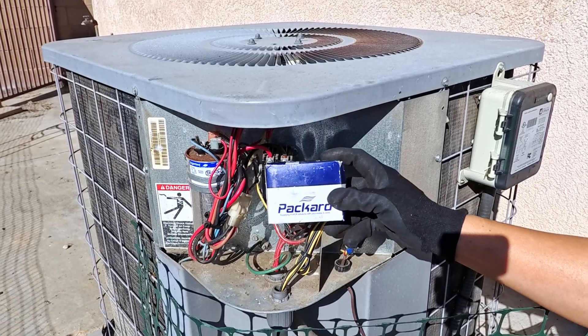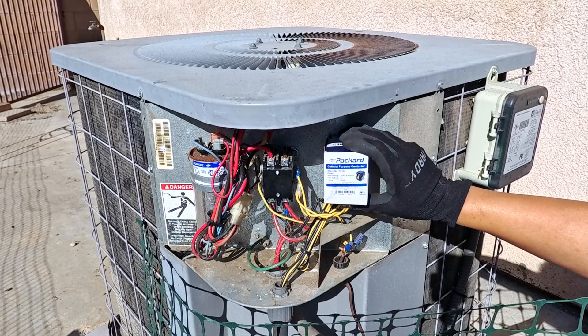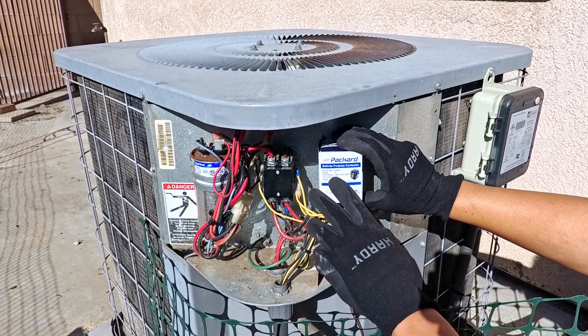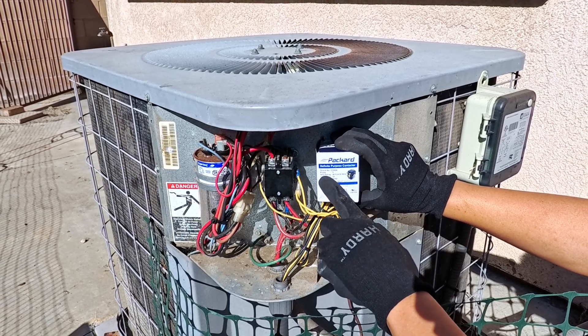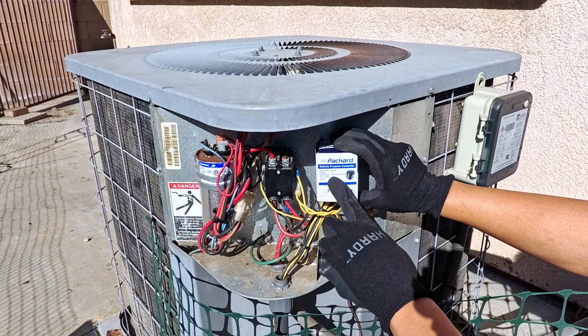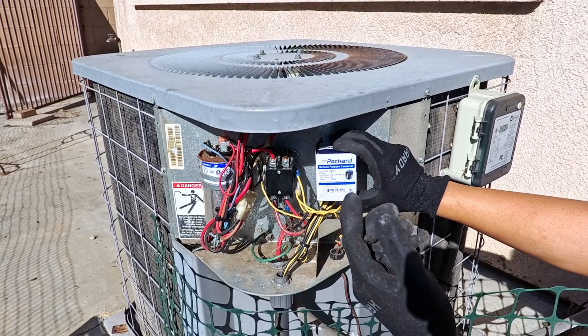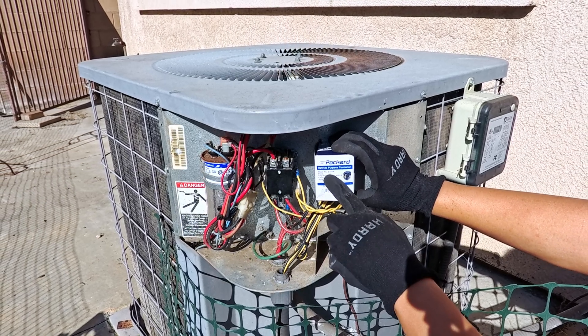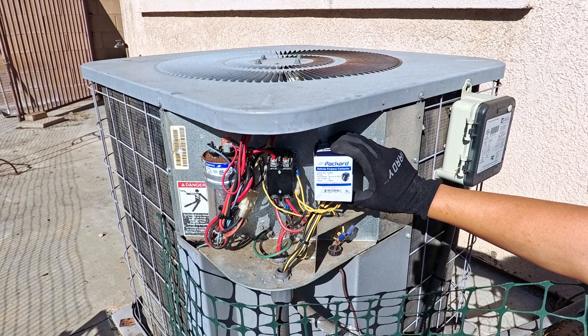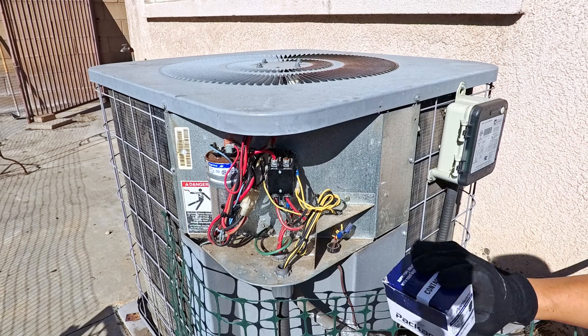Here is the new unit — same brand, Packard. Everything matches up: two poles and 24 volts. The amp rating is also important — this one is 40 FLA, 50 res, and 50/60 hertz. The model number of this part is C240A if you are interested. Again, link in the description below. Let's go ahead and swap these wires.